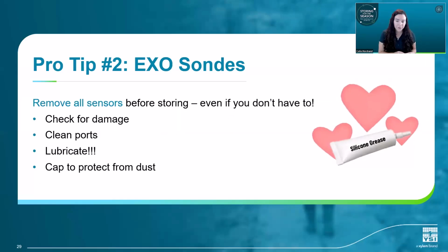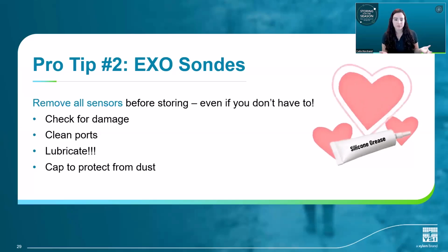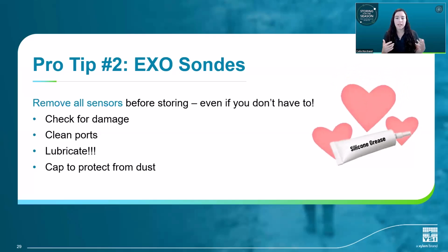And here's my hot tip for you if you have an EXO. I always suggest removing all your sensors from your bulkhead before you store for a long period, even if you don't have to for their specific storage requirements, because it gives you an opportunity to check everything for damage, clean the ports, and perform maintenance on all the wet mate connectors and the O-rings. And remember that if you have an EXO, you love grease, so lubricate your connectors. And this is any silicone O-ring grease that you can get at a hardware store.